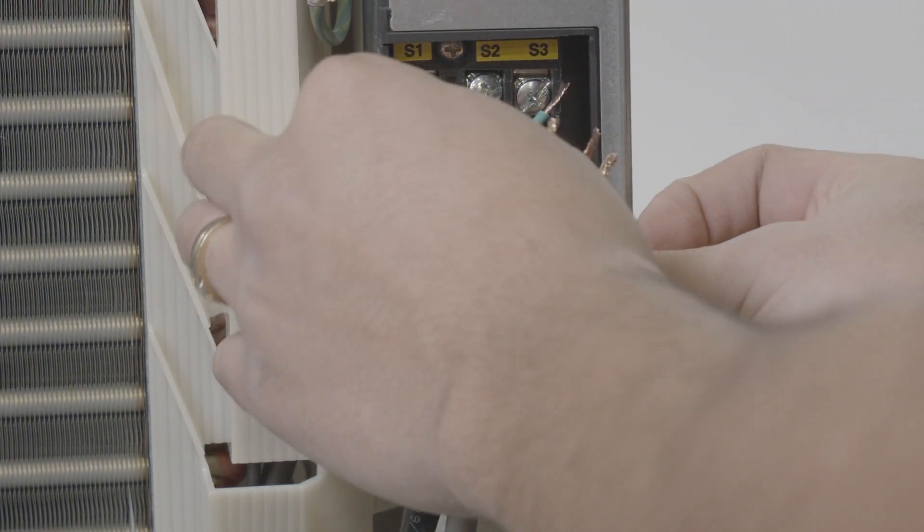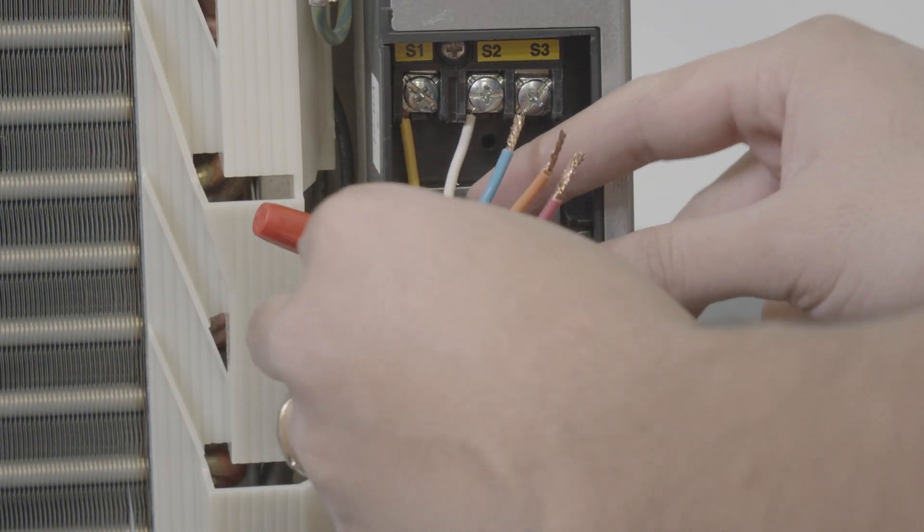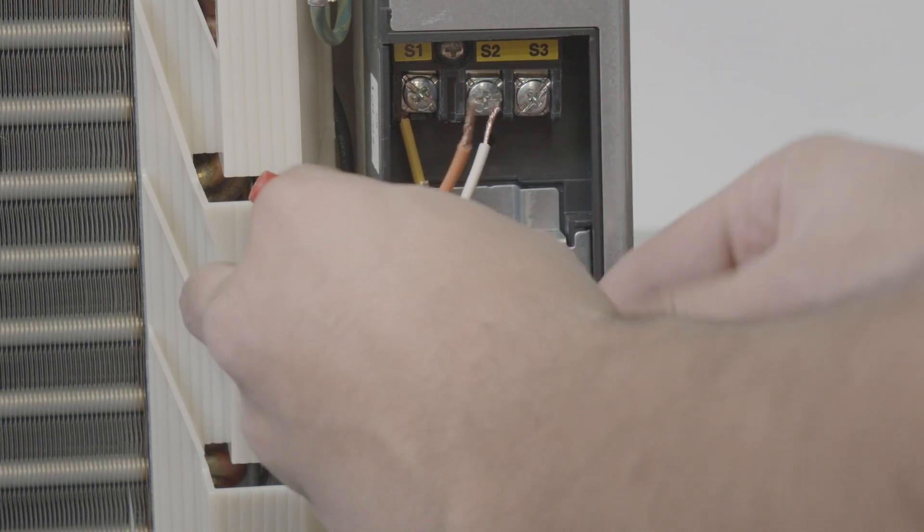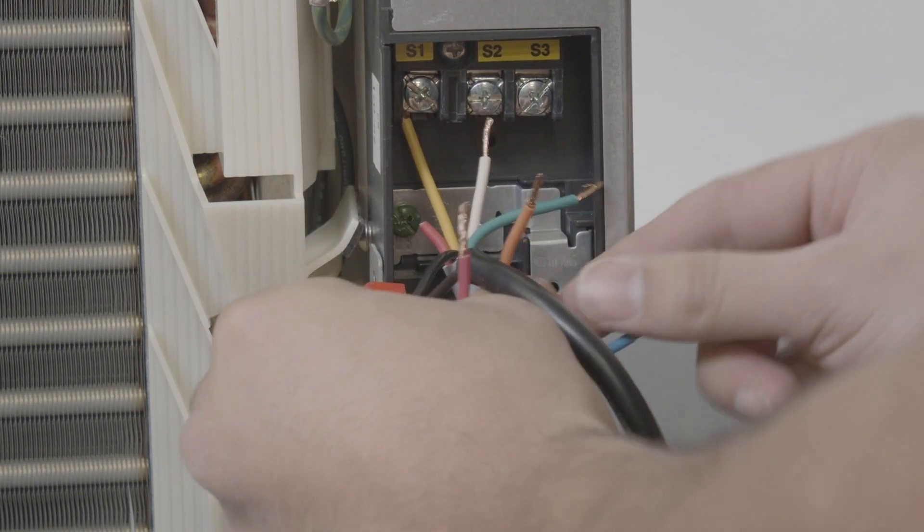For the S2 terminal, you need to terminate both the white line voltage wire powering up the pump and the S2 wire coming from the outdoor unit.